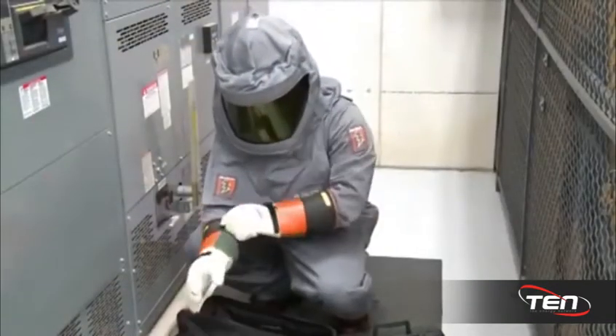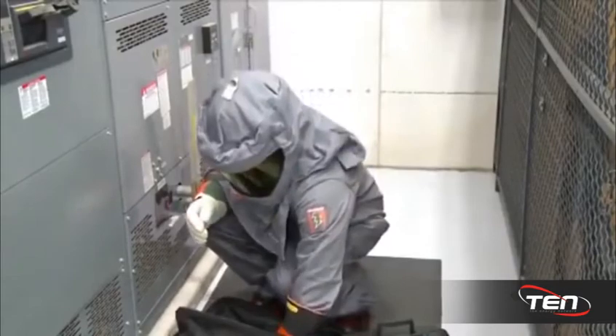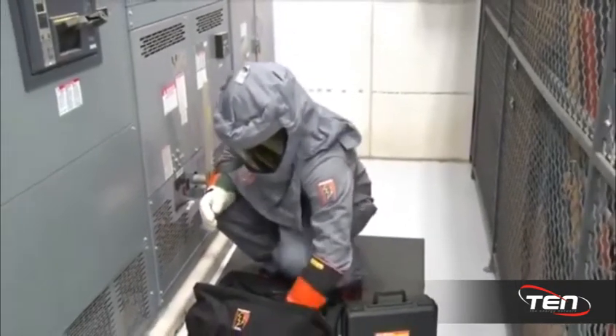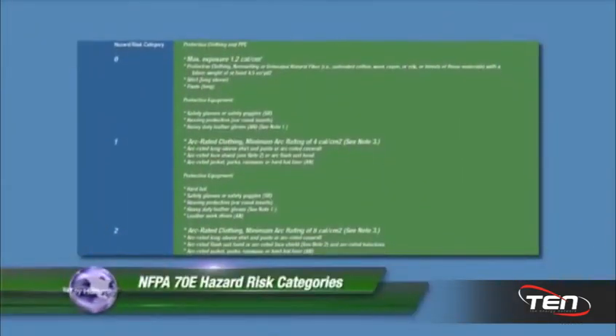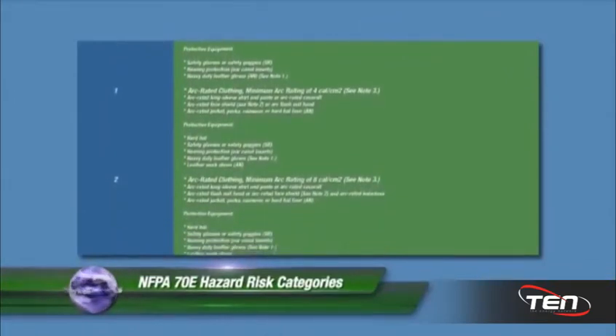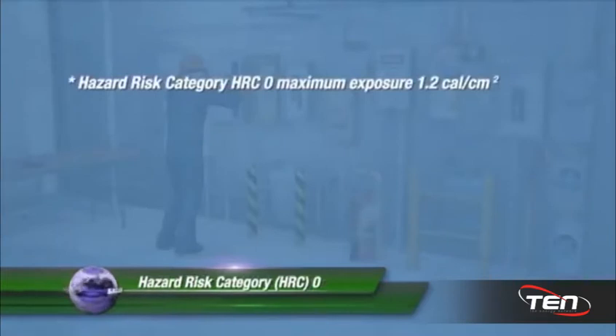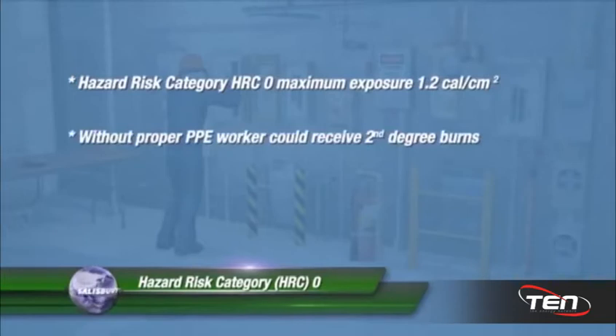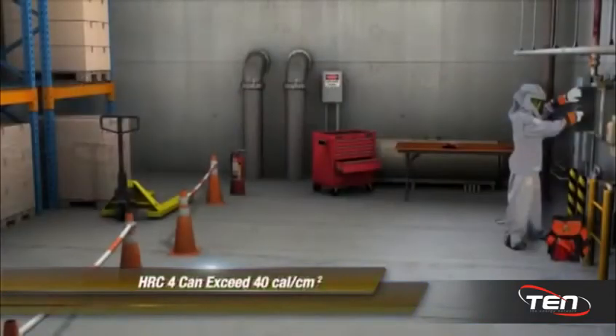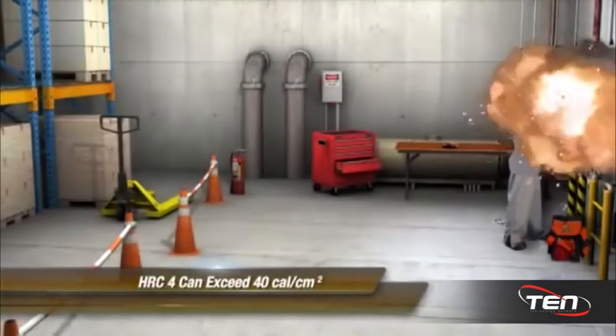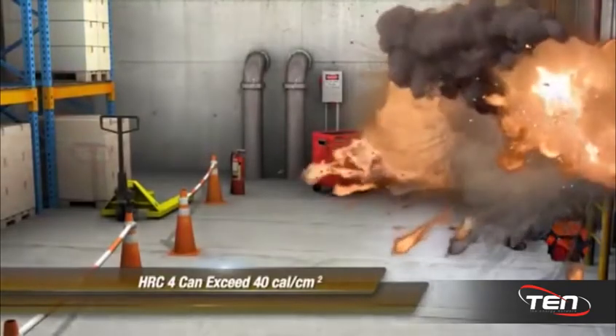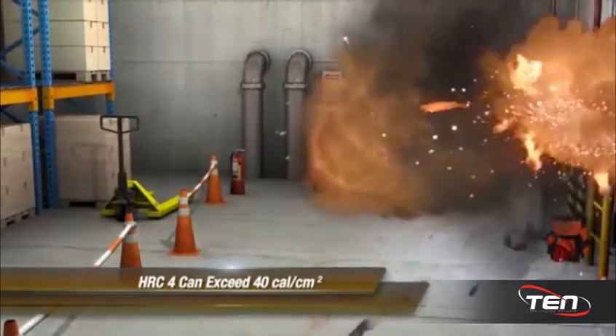Once your shock and arc flash assessment is complete, you will know the hazard risk category or arc rating for that location. NFPA 70E 2012 breaks down arc flash hazards into multiple hazard risk categories. HRC 0 has a maximum exposure of 1.2 cal per centimeter squared. Without the proper arc-rated PPE, an electrical worker could receive a second-degree burn from an HRC 0 exposure. At HRC 4, exposures can exceed 40 cal per centimeter squared, where the risks are more catastrophic.